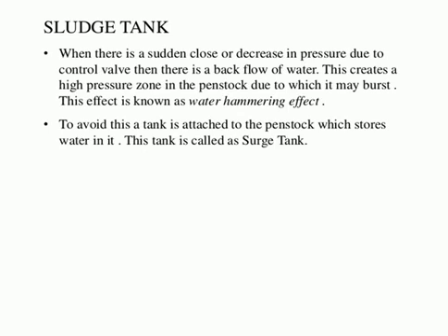Now surge tank. Surge tank also plays an important role in a hydropower plant. When there is a sudden closure or decrease in pressure due to the control valve, then there is a backflow of water. This creates a high pressure zone in the penstock, due to which it may burst. This effect is known as water hammering effect. To avoid this, a tank is attached to the penstock which stores water in it. This tank is called the surge tank.